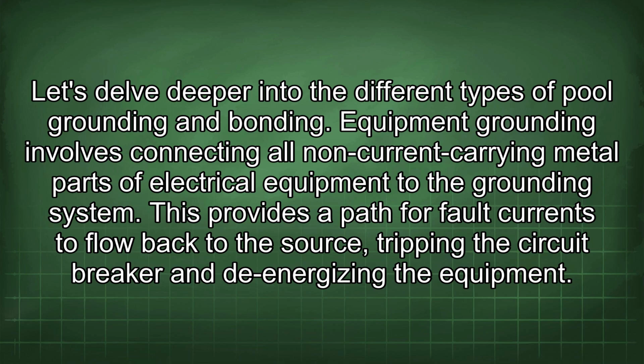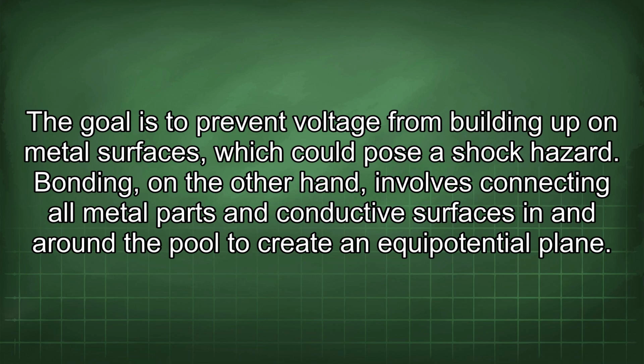Equipment grounding involves connecting all non-current carrying metal parts of electrical equipment to the grounding system. This provides a path for fault currents to flow back to the source, tripping the circuit breaker and de-energizing the equipment. The goal is to prevent voltage from building up on metal surfaces, which could pose a shock hazard.